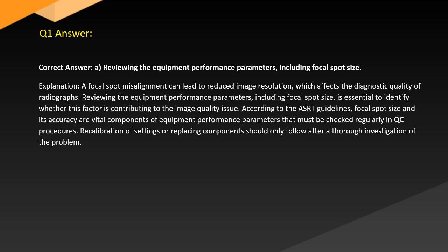image quality issue. According to the ASRT guidelines, focal spot size and its alignment are vital components of equipment performance parameters that must be checked regularly in QC procedures. Recalibration of settings or replacing components should only follow after a thorough investigation of the problem.